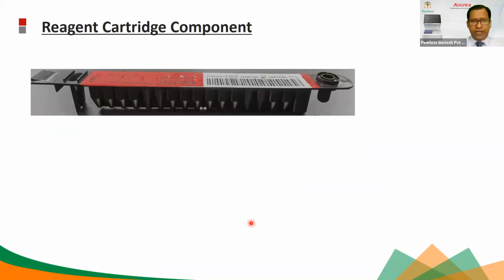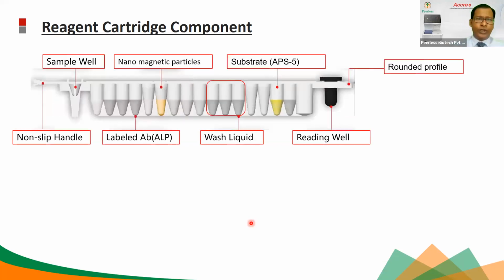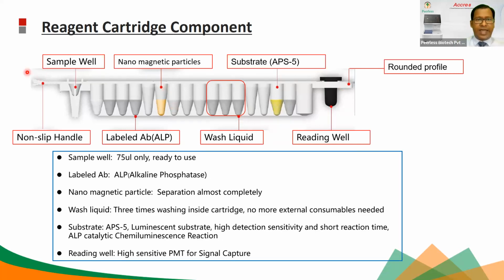And this is the original kit, original cartridge. And once you see the cartridge properly, you can see it like this. I'm clicking next. Have a look. So here is the sample well. It is the handle from where they can handle. And here is the labeled antibody, which is the antibody coated with ALP, alkaline phosphatase. Here the nanomagnetic particles are provided inside the cartridge, and a few are free because during the multiple steps of washing, the free ones are required. And for multiple assays, multiple cuvettes may be required. Now here the wash solution is provided in these 3 cuvettes in the cartridge. And here the APS substrate is provided in the last part. And at last, the reading well. So this is the full cartridge which contains everything. So the sample well is 75 microliters, as I say. Okay. So only a 75 microliter sample is required.